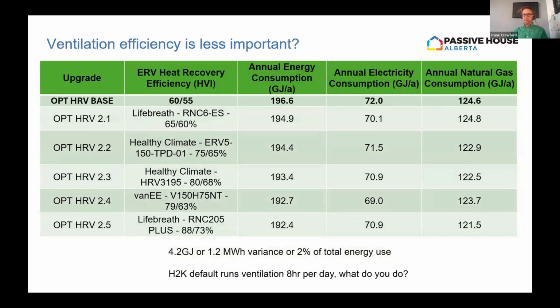Next we look at ventilation. We had them run scenarios between a 60% efficient ERV and a roughly 90% efficient ERV. Interestingly, the variance was not that much - only 4.2 gigajoules, which is still 1.2 megawatt-hours, but only 2% of the total energy. This is different from what we're used to seeing in Passive House, where ventilation is much more important.